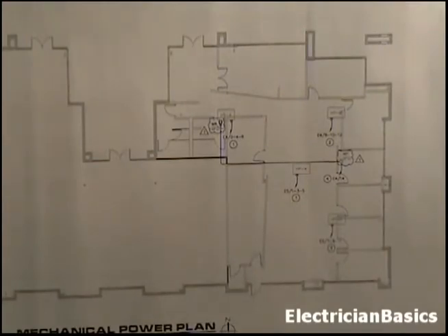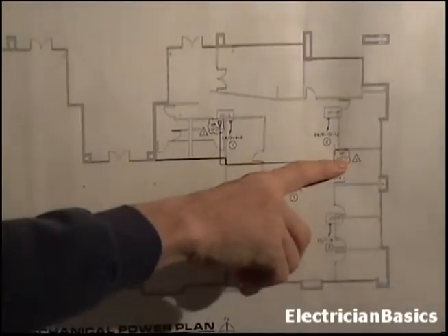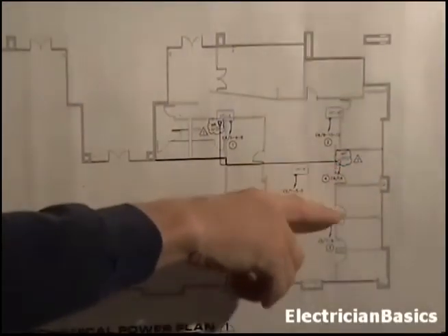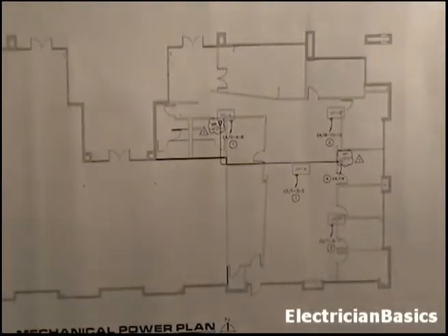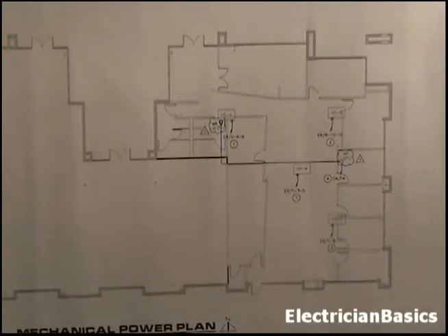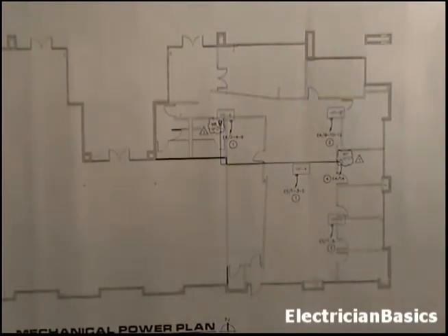Now let's take a look here. It says WP. From our abbreviations, we know that that means weatherproof. And GFCI is a ground fault current interrupter. And so it's a GFCI plug, and it's a weatherproof outlet. So that's what that takes to make that work. Let's refer to note 6 right now. It says, all exterior receptacles shall be furnished with a Tay-Mac cover. So we have these 2 receptacles here. You might be tempted, if you don't read this note, to just put the standard Bell cover over it. Bell is a common name for a company that makes weatherproof boxes. A Tay-Mac cover is different, and this is what this is calling for. So you have to read these details and make sure you install the right features.